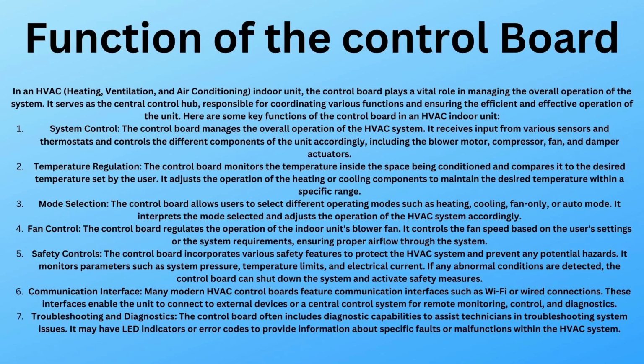Mode selection. The control board allows users to select different operation modes, such as heating, cooling, fan only, or auto mode. It interprets the mode selected and adjusts the operation of the HVAC system accordingly. Some of these you can actually set when you get the pamphlet and open up the operations of that control board; you can set it to do different things. You can set it for auto mode, because a lot of thermostats nowadays on the wall have an auto setting where you can set your heating temperature, say 72 degrees in the winter, and in the summer you might want 75. Once you program those two in, you can hit auto, and it'll fundamentally control itself, deciding if the heat or the cool needs to come on, depending on the temperature within your home.